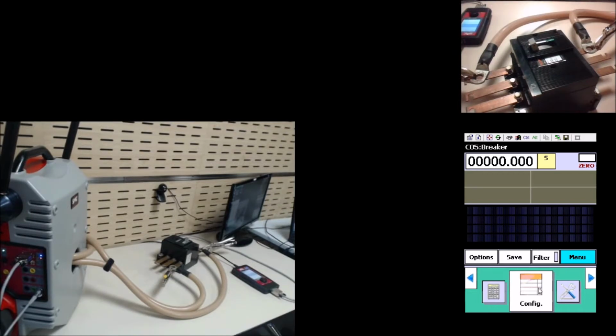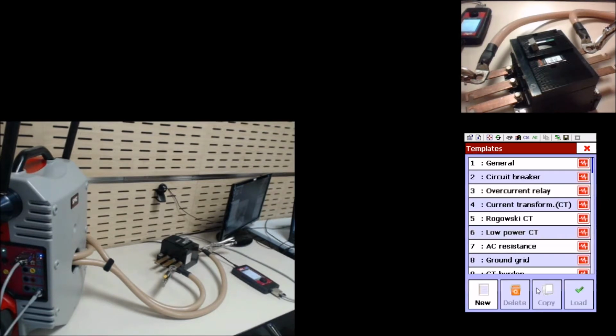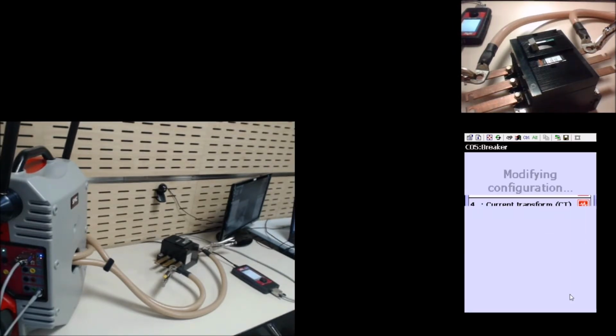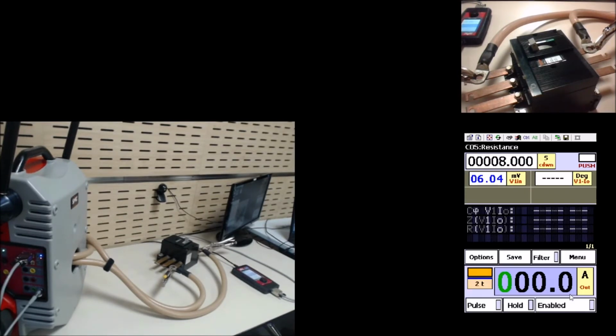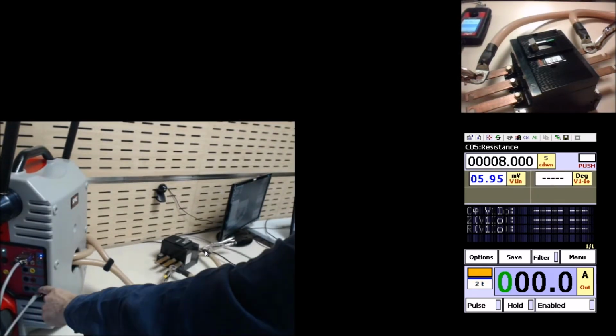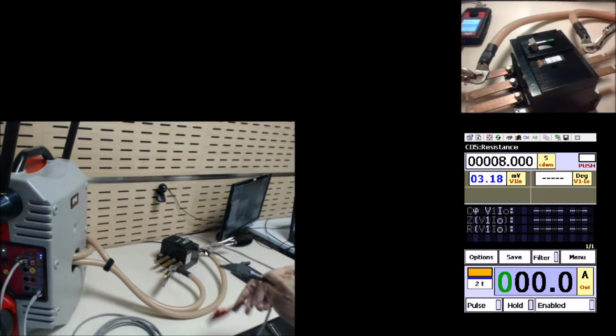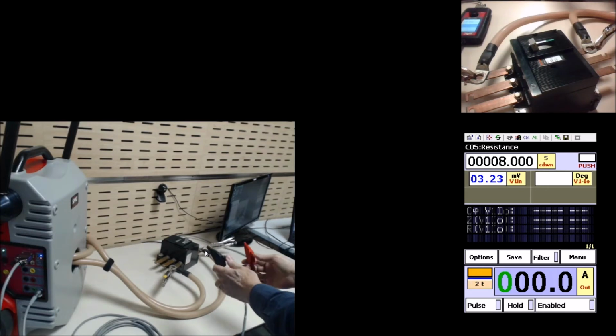So now I'm selecting one of the test templates, which is the contact resistance template. So you see there's a template named AC resistance, and this is the template we are going to use to check the contact resistance in the connected phase of the circuit breaker here. Okay, so you see we have the current connections already made. We only need to add the voltage connections. So we are just taking this cable from the high sensitivity voltage input here, and connecting the voltage measurement terminals to each side of the phase.